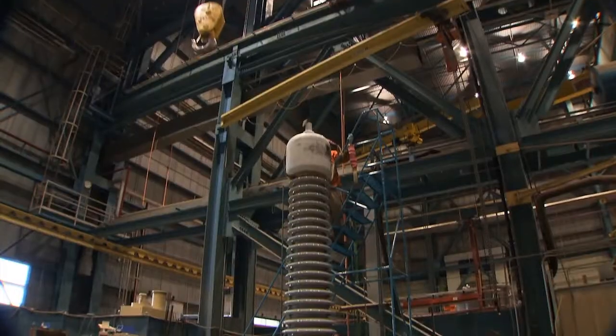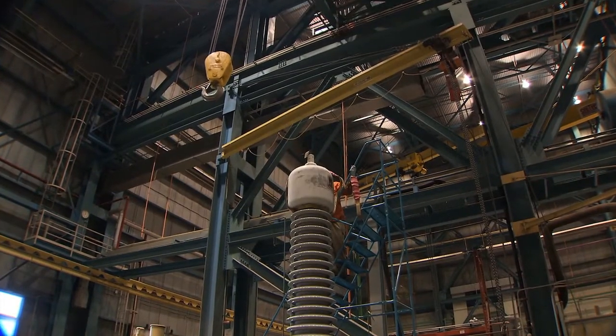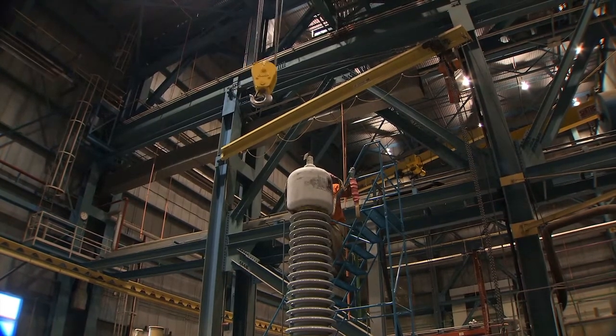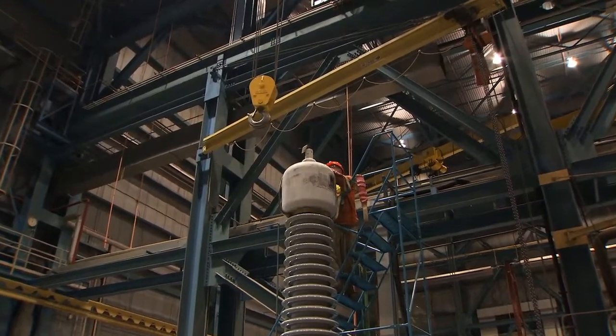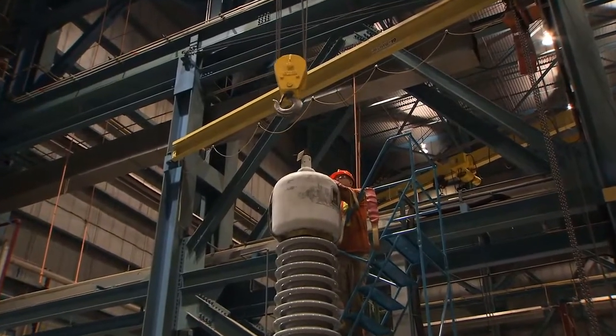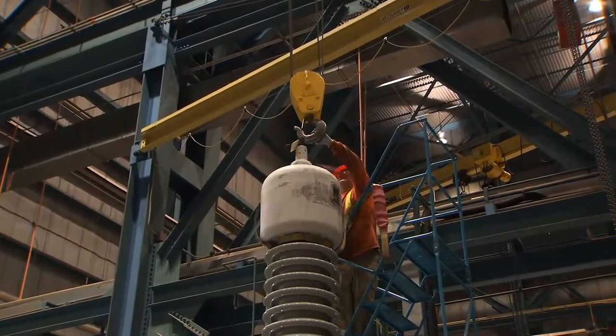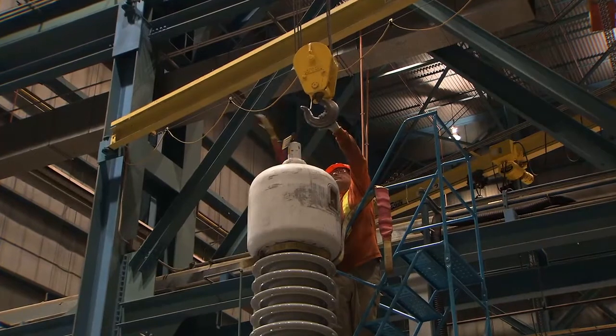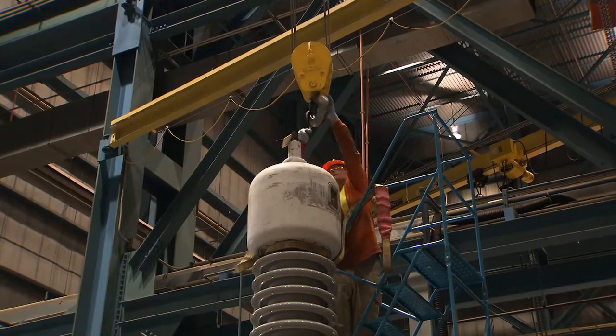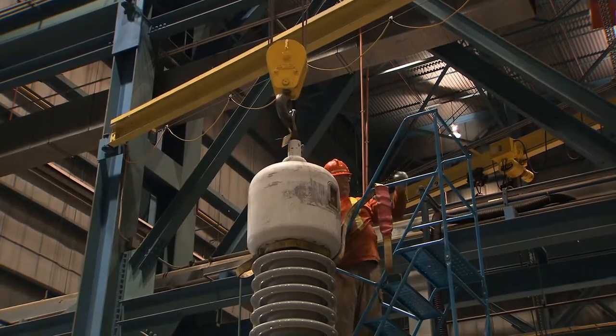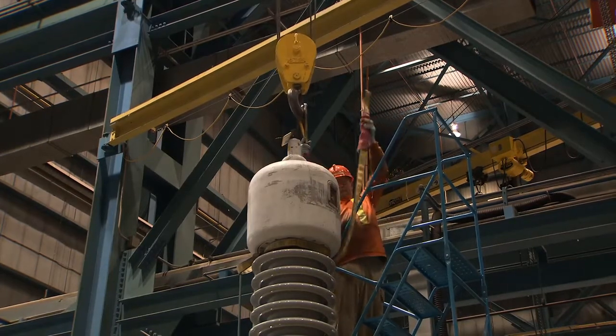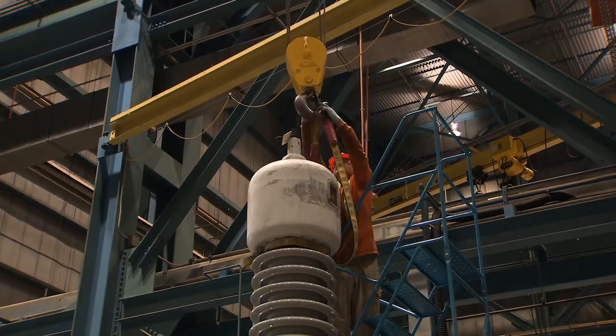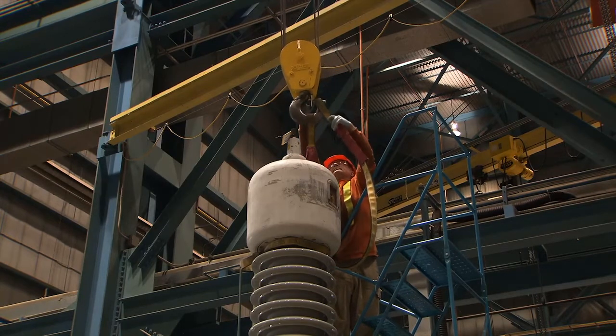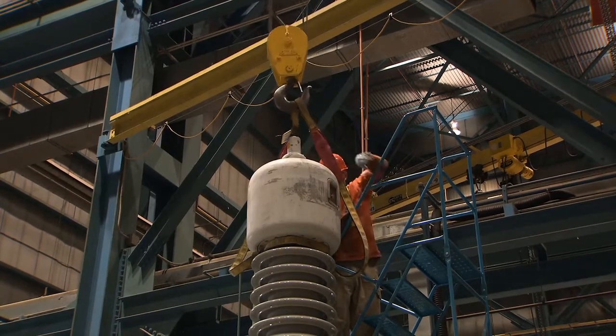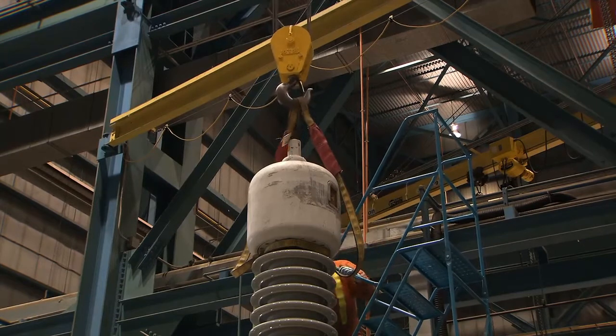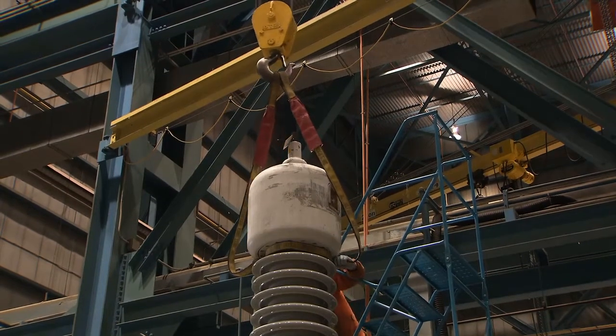Using a rolling warehouse ladder with railings and the locking system engaged, choke another sling over the top of the sling that is already choked around the porcelain under the oil reservoir tank at the top of the bushing. Ensure both slings are on opposite sides of the oil reservoir tank in order to optimize conditions for a balanced lift off the floor. Attach the ends of both slings to the hoist hook.